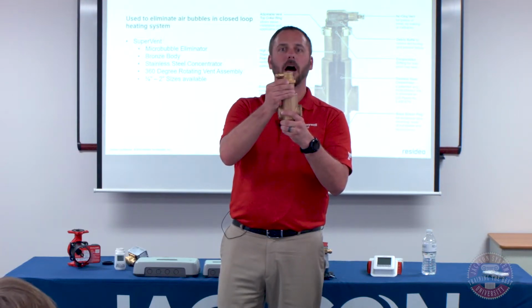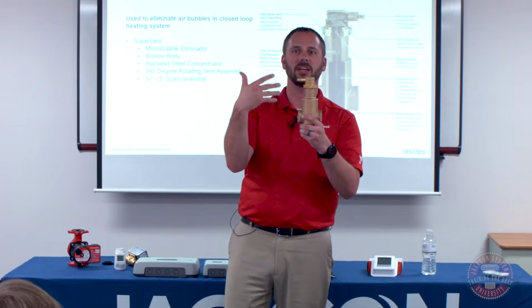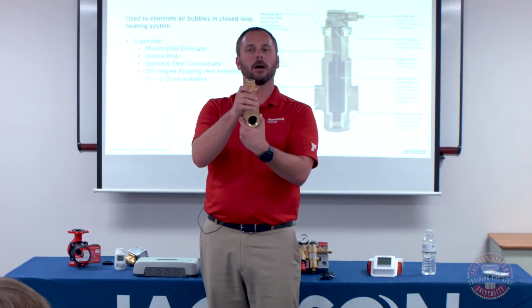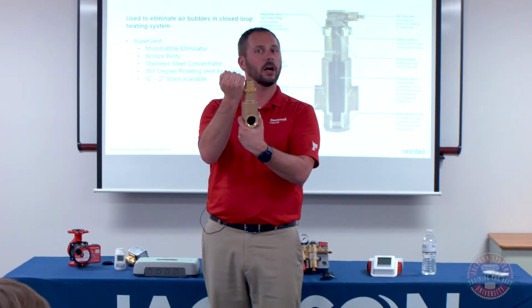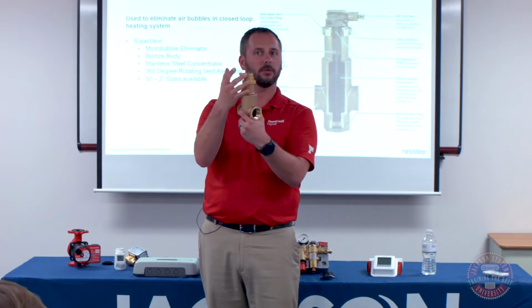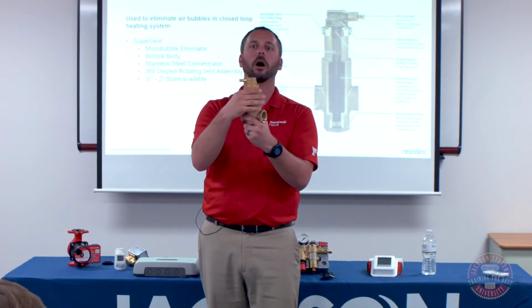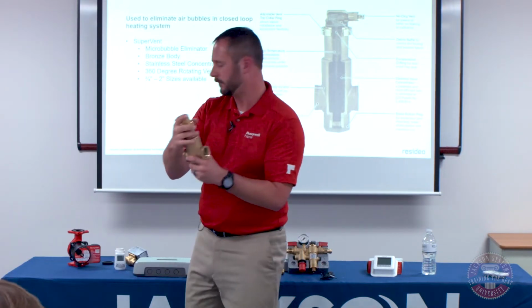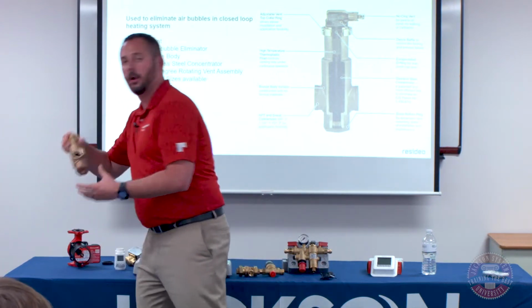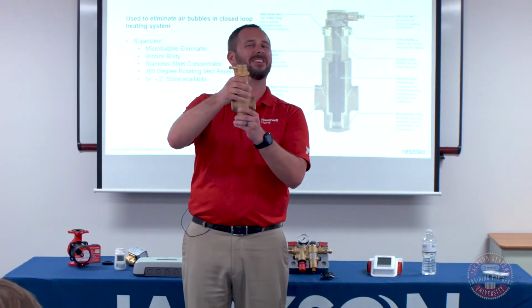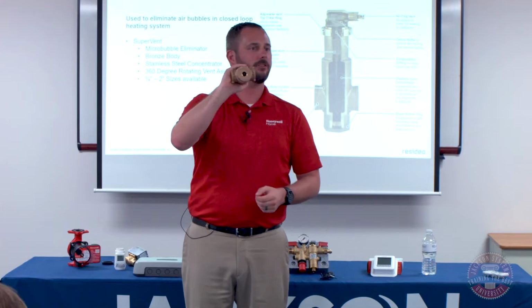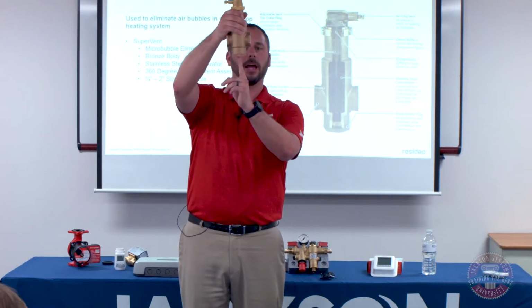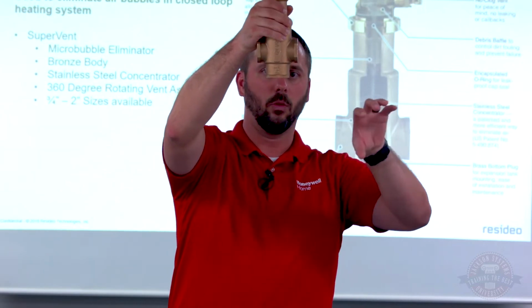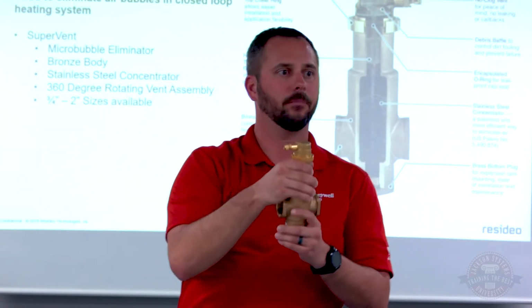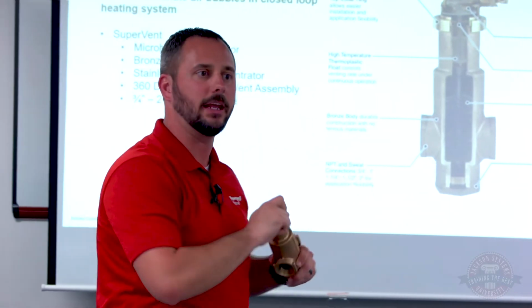Every now and then it's possible, especially with glycol, because it can be sticky, especially around air, for that float to get stuck inside of there, but that's as simple as taking this apart, cleaning this off with fresh water, and putting it back together. And then off the bottom, I was talking about hooking everything up with half-inch. We have half-inch connections here at the bottom. Typically, you have a half-inch pipe coming down, an expansion tank hanging here, and your water makeup coming from either side. And I think we've got a question from the audience.